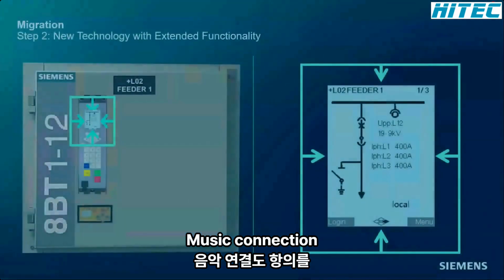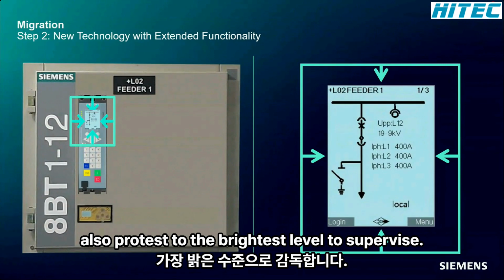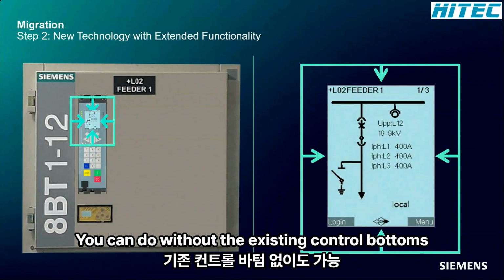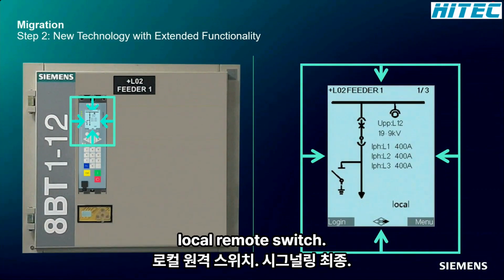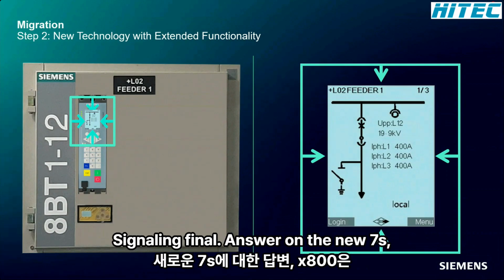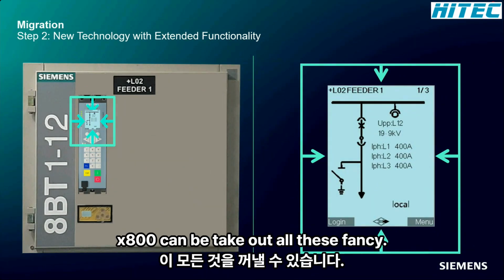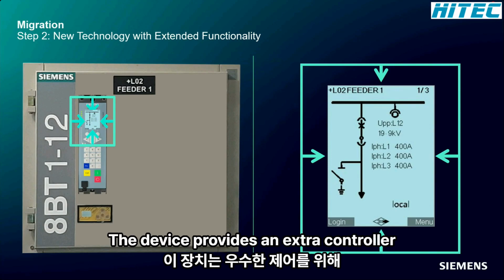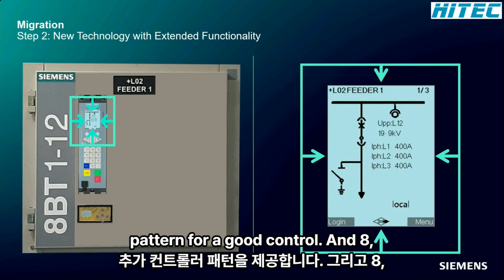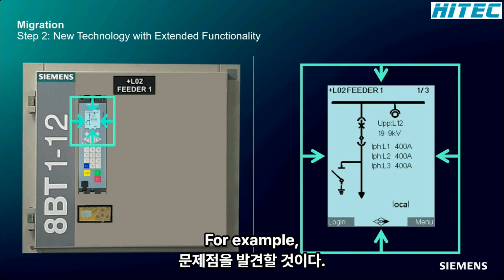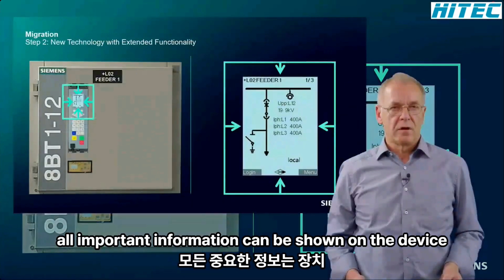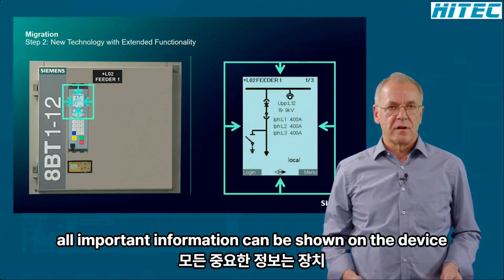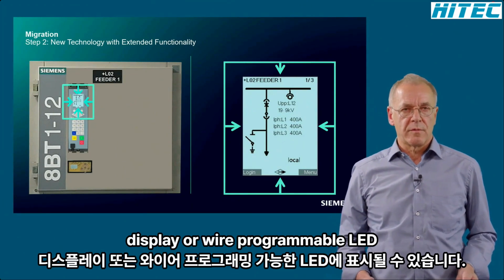With the connection of the process level to the device, you can do without the existing control buttons, local remote switch, signaling panel, and so on. The new 7SX800 can take over all these functions. The device provides an extra control button for circuit breaker control and 8 programmable function buttons, for example, remote or local control. All important information can be shown on the device display or via programmable LEDs.